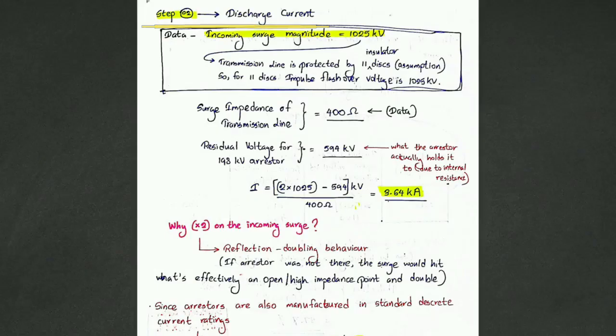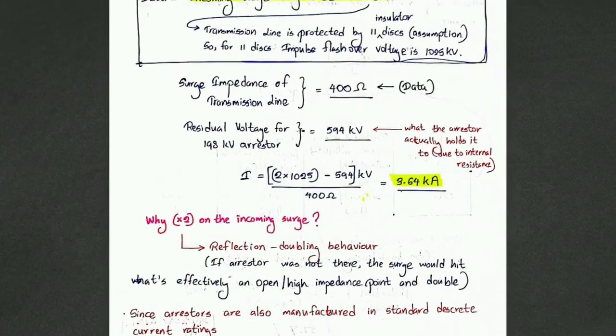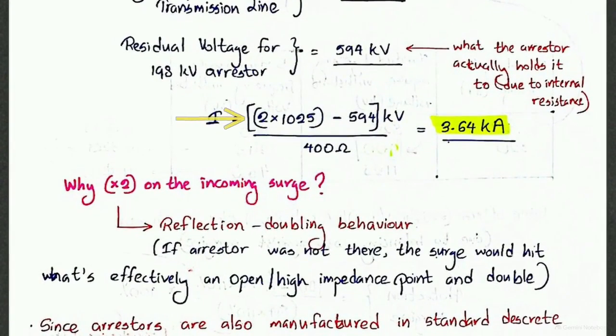Step 2 dictates our discharge current. This handwritten calculation factors in an assumed incoming surge magnitude of 1,025 kilovolts, the 594 kilovolt residual voltage, and the line impedance. Looking at the formula, note the specific multiplier here, times 2. This is a critical factor in the physics of the system.